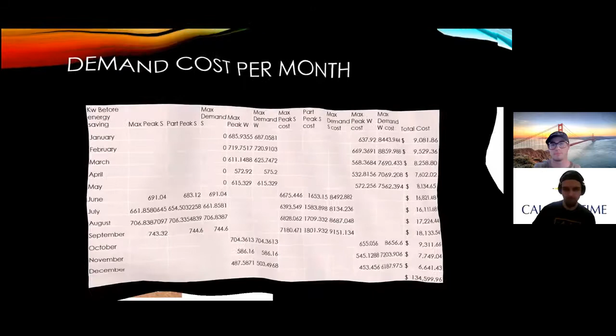Our initial plan to cut these costs was to implement a combination system of solar panels and flywheels. Flywheels work by taking a 5,000-pound steel disc and spinning it up to about 50,000 RPM on its motor generator shaft, which is sealed in a vacuum cylinder with hybrid electromagnet bearings to reduce friction.